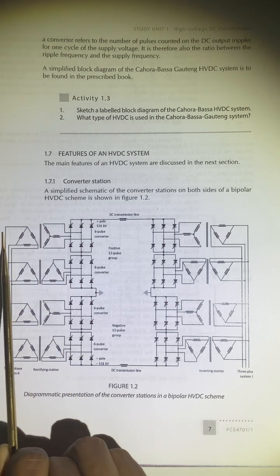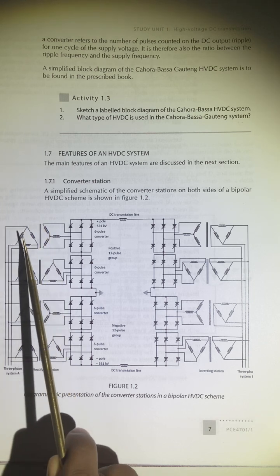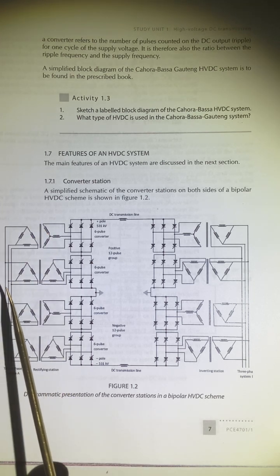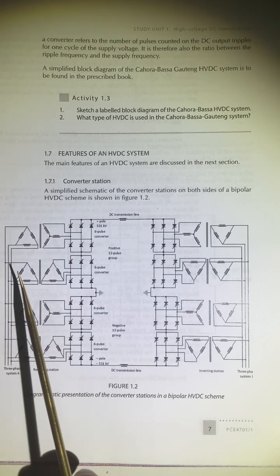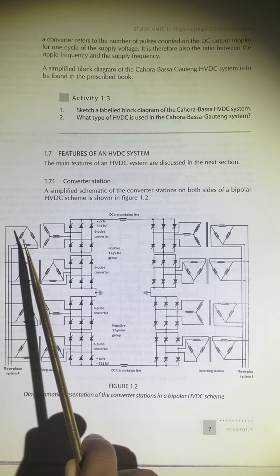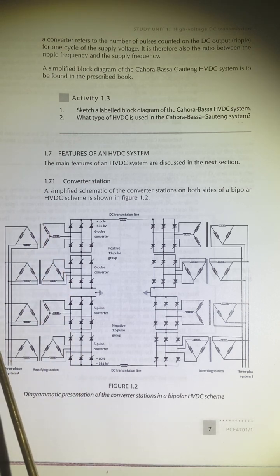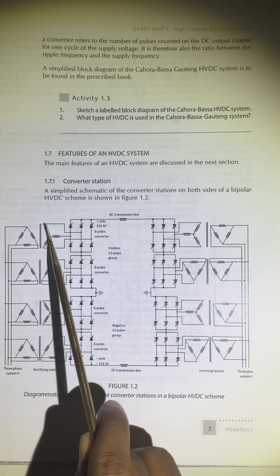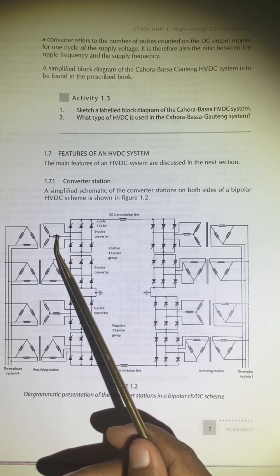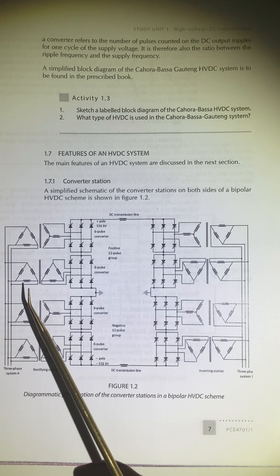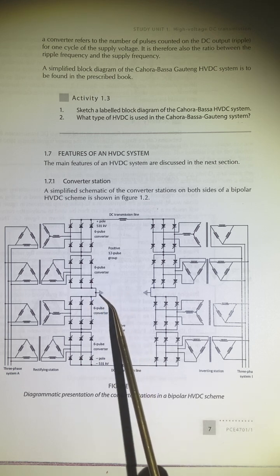The three-phase system A input uses a delta-delta configuration on the primary side. On the secondary side it is delta-star and delta-delta. On a delta-delta system the phase shift is zero degrees; however, for a delta-star configuration, it is a 30-degree phase shift relative to the delta-delta system. These two converters are connected in series and also connected via ground.